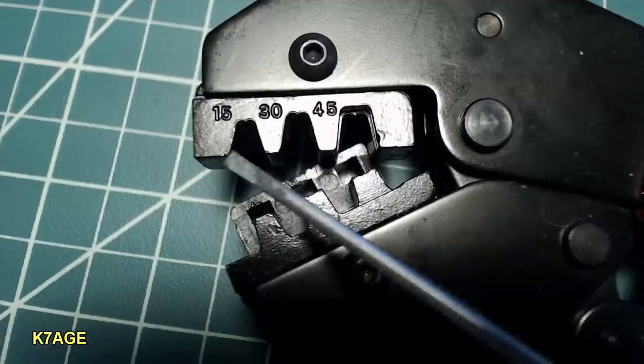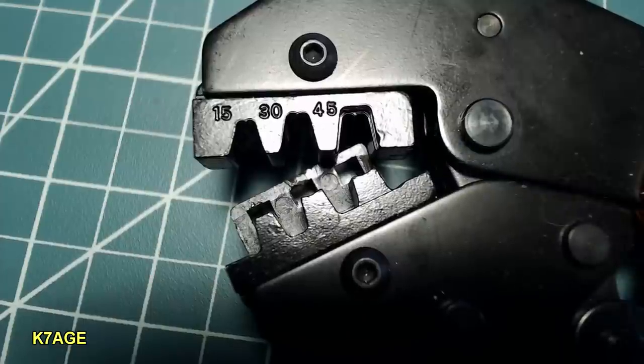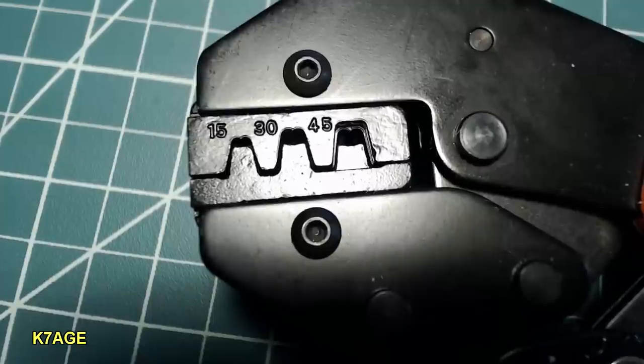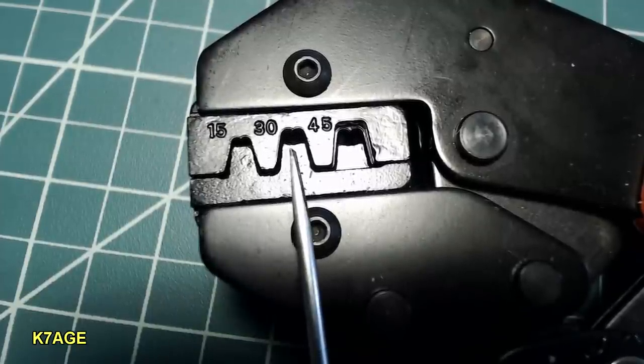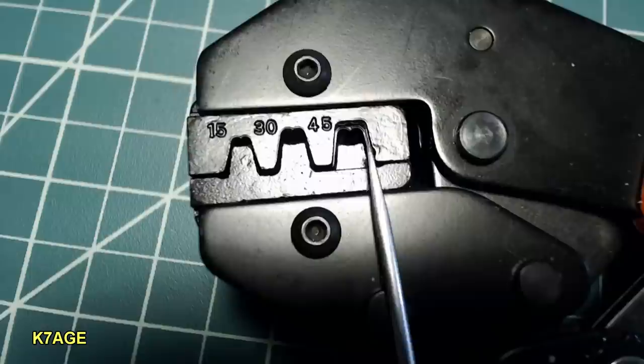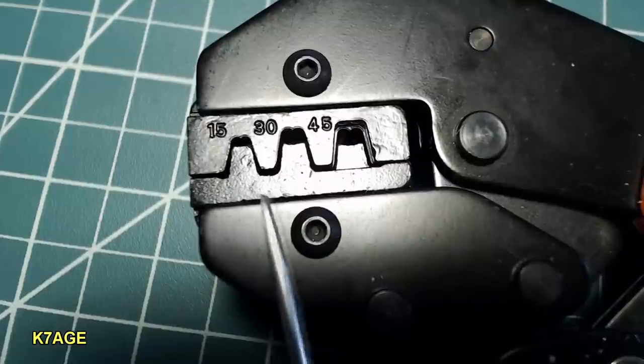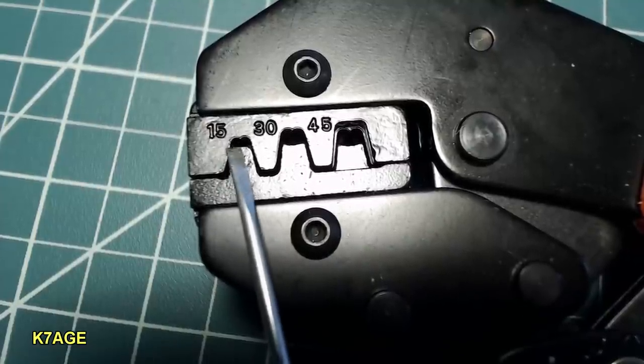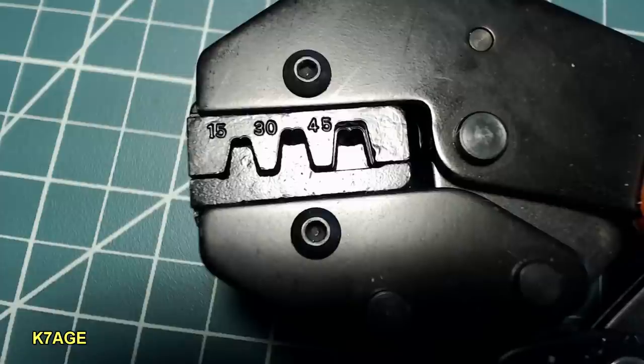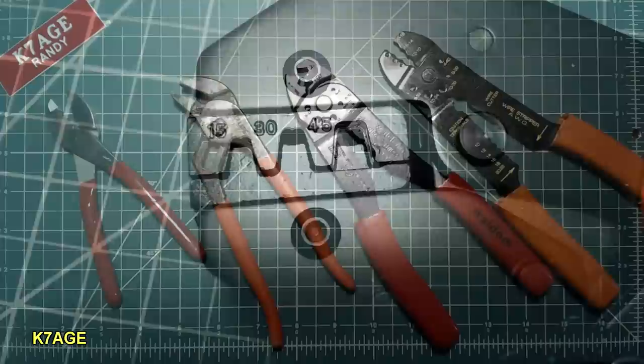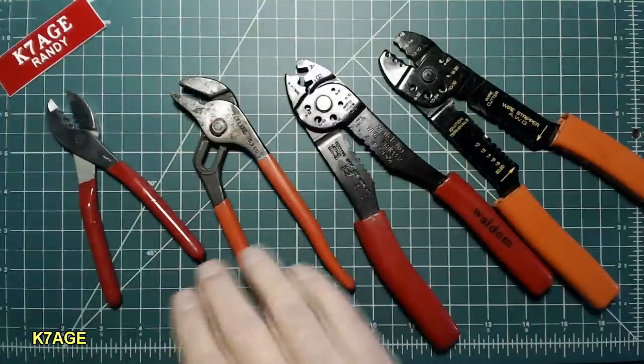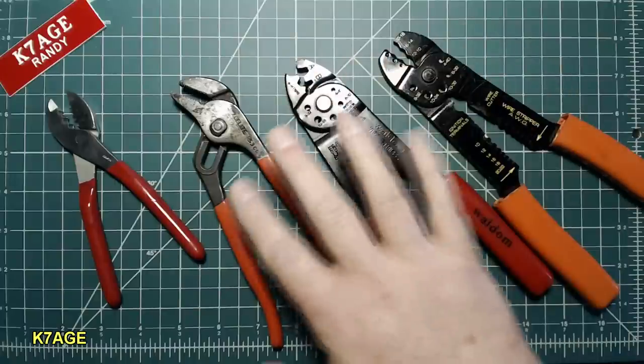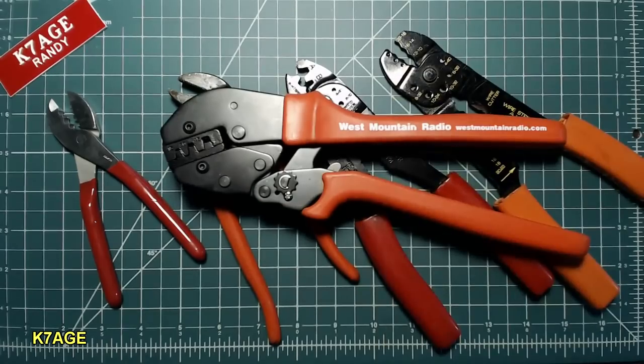Okay, this crimp tool has a die in it, installed in it, and it has three cavities. One for the 15 amp, the second for the 30 amp, and the third for the 45 amp connector pin. And as I close this down, you can see that we'll be closing really tight on the 15 amp as compared to the 30 and less tight on the 45. And this is because of the different amount of wire that's going to be inside the pin. So you have to make sure we get the right pin with the right wire size in the right cavity. And you can see the close-up of the die here, the shape, where it has these curved areas which bends it kind of back on itself to ensure the crimp connector has the correct shape so it fits correctly inside the plastic shell. Some guys will say you don't need the expensive crimp tool that you can crimp the pins with a pair of channel locks or some of these other tools that you may have in your toolbox. I've never been able to obtain consistent, repeatable results with these things. I'll take my good old ratchet crimp tool any day.